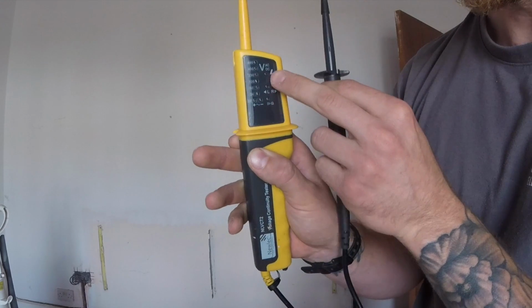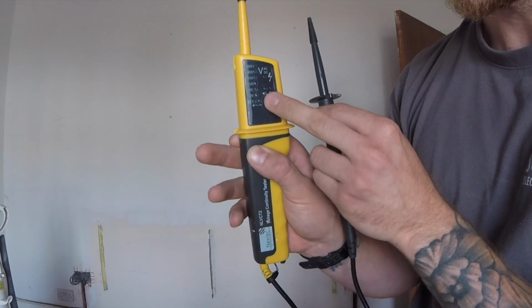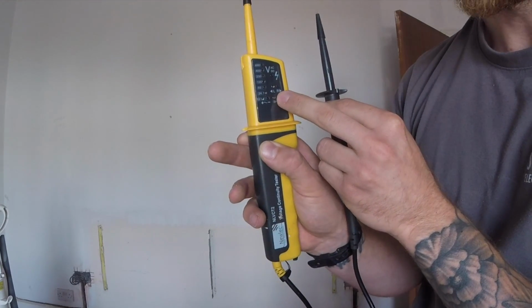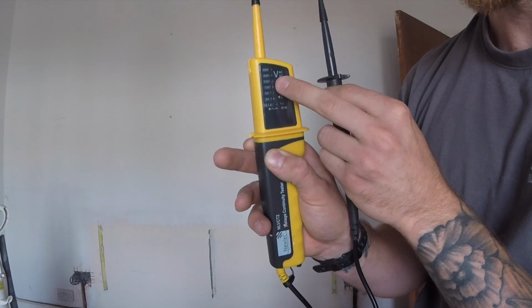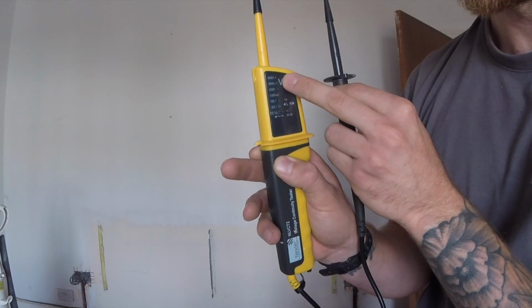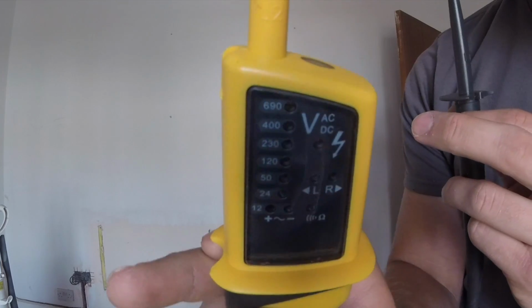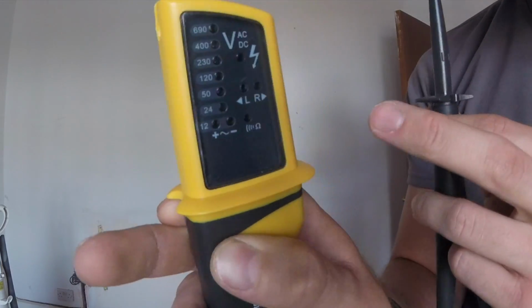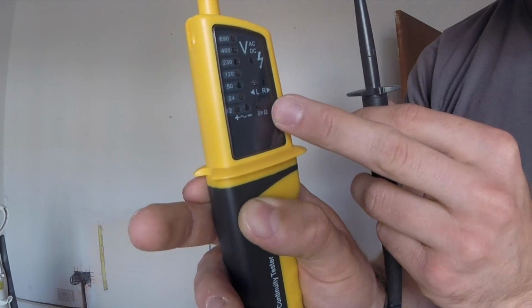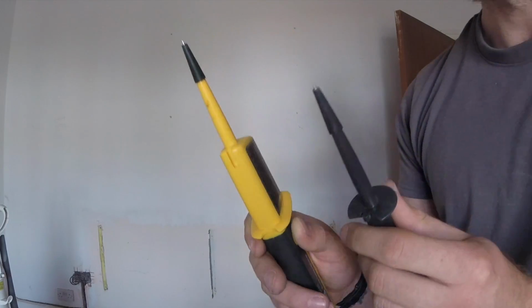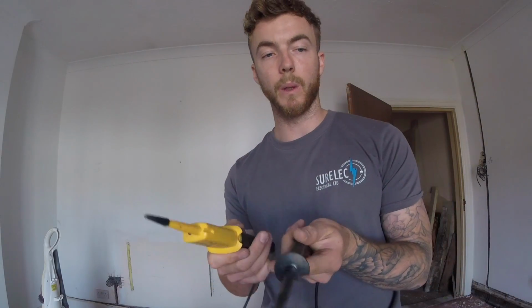And then all it is, little LEDs on here will let you know the voltage it is. So it starts off at 12 volts, 24 volts, 50 volts, 120 volts, 230 volts, 400 volts, and then 690 volts, as you can see on there. It also gives you a little audible tone as well when you're on live terminals.